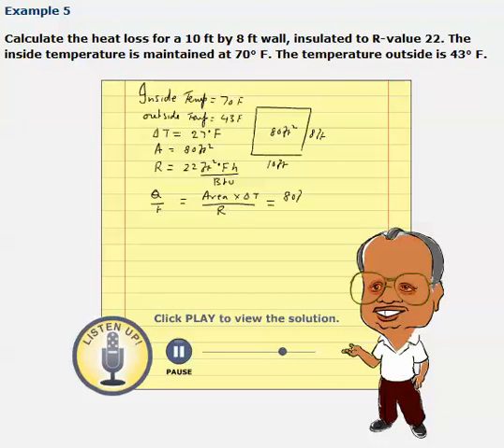it is 80 foot square times 27 degrees Fahrenheit divided by 22 R value, foot square degrees Fahrenheit hour over BTU. So this will be equal to, here you can cancel foot square, foot square, degrees Fahrenheit, degrees Fahrenheit. We are left with BTUs per hour.